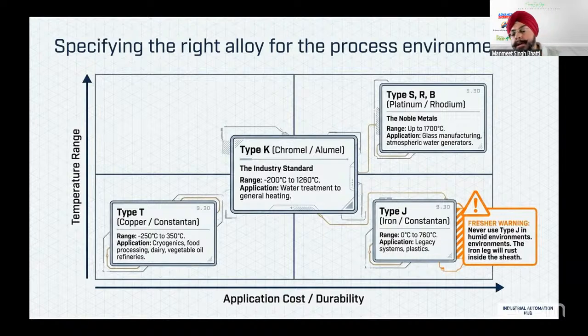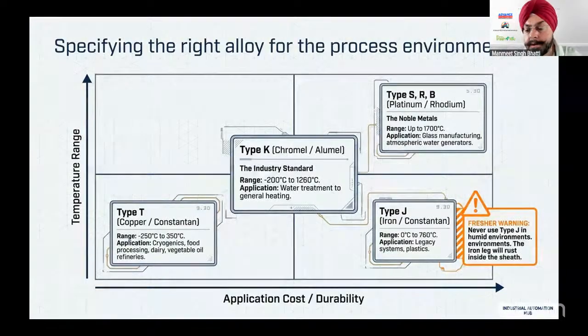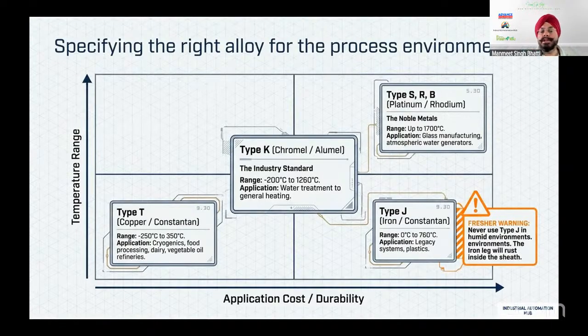Type J is used where we get temperatures of 0 to 760 degrees. Type J is a little cheaper kind of thermocouple, as people call it. So you will find the industry using either J-type or K-type thermocouple. But J-type has a ferrous component, an iron component. The biggest problem here is the durability of the thermocouple, because if some moisture comes in the line, you will find that iron connection getting corroded. That corrosion happens very fast. So be very clear on what you want to use and where you want to use it.